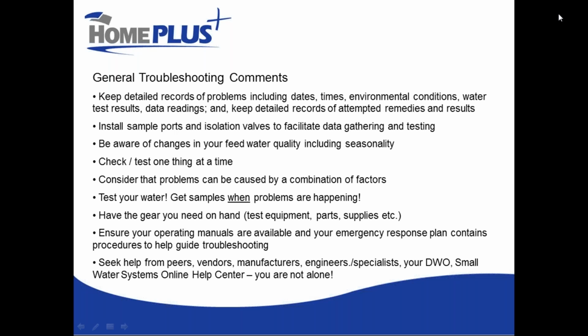And we will talk about a couple of examples of that, but one I can give you right now is, say, for instance, you have a UV intensity alarm saying that your UV dose is dropping below a safe level. That could be a combination of having an old, weak lamp that's on its last few months, poor feed water quality, and a degraded, older UV sensor that's also starting to fail. Sometimes replacing or fixing one of those problems might be enough to get you out of your immediate alarm condition, but it hasn't truly addressed all of the factors. So you're setting yourself up for an inevitable troubleshooting job again in the near future as one of those other things becomes more severe.